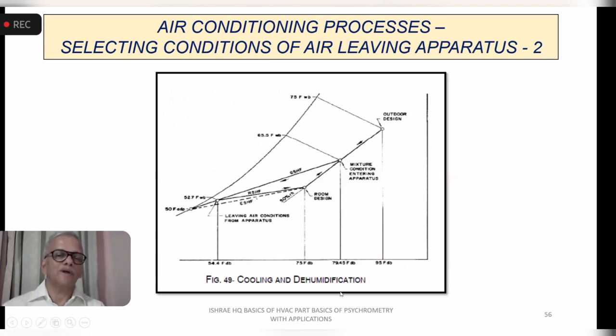Same parameters repeated for the cooling and dehumidification with the numbers here for the calculation. This is from the example. We are not having enough time to go and solve an example, but these are the values which tell you, okay, this is how the calculations are done. So you take the room design temperature, outdoor design temperature, airflow rate calculated for the dehumidified rise, which is indicated. And then with the sensible heat factors, you calculate the ADP and the coil. So that is the leaving air condition for the apparatus. So this is how you select the equipment.